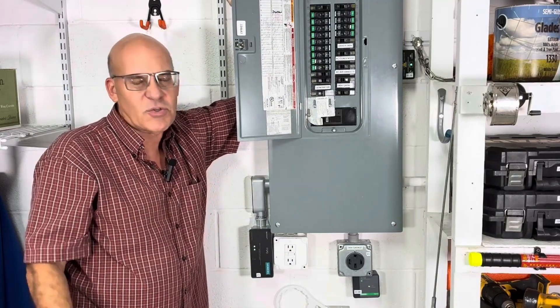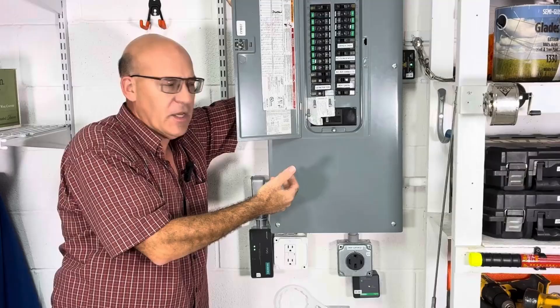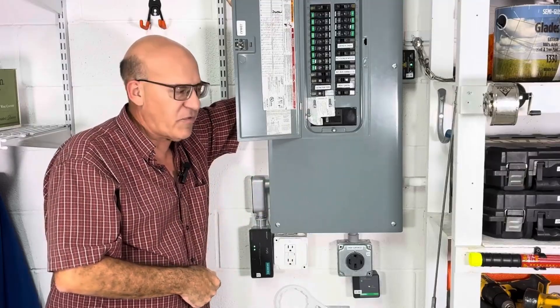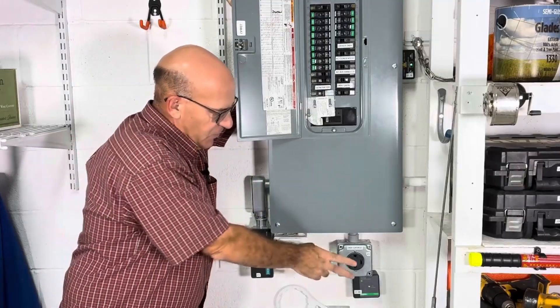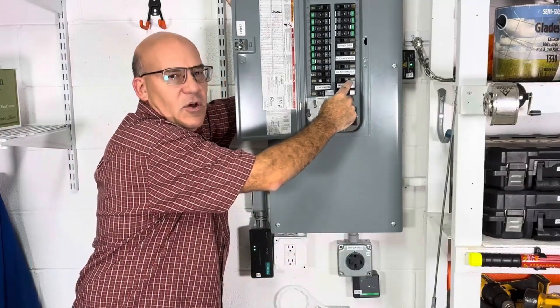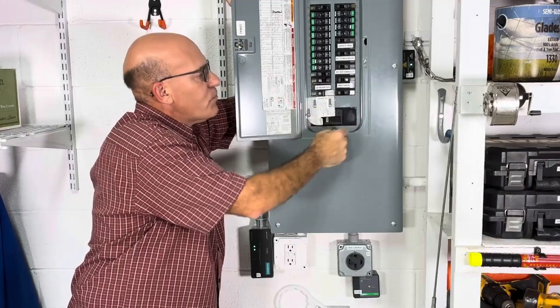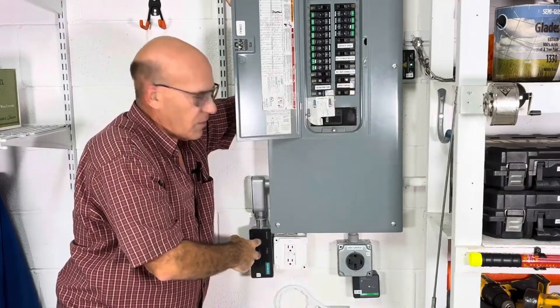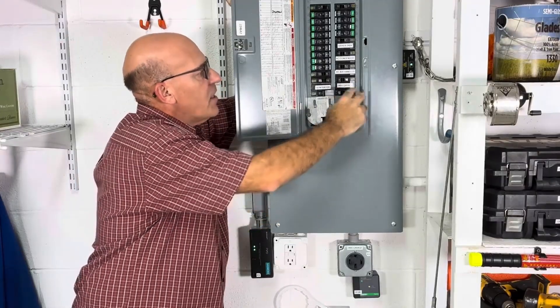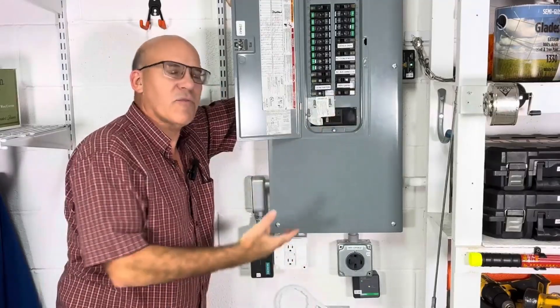We'll open this box up in a minute. Basically the power comes in from FPL — that's Florida Power and Light, our electric provider. We have a 50-amp plug here and that breaker is located right here. It's the lowest breaker we've got, beside our generator interlock. So we've taken this and run the two hot wires up to this breaker, the neutral to the neutral bar, and the ground to the ground bar.